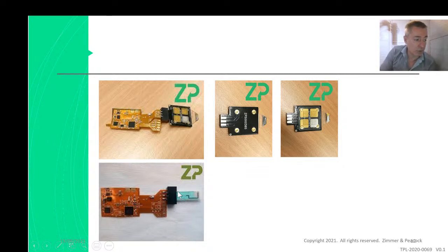And you put the sensor into the connector, and then this end here will have to go into the glucose solution, or these microneedles here. What we do is we often test these kind of things on animal skin that we get from the abattoir. We'll get a petri dish, fill it full of glucose, and then put the microneedles into the skin and essentially test the microneedles that way. So that's one way of getting going with this.